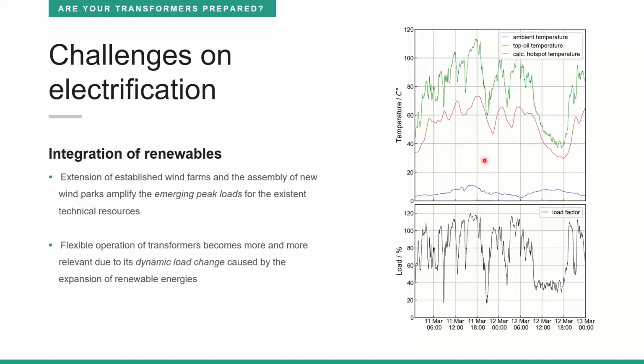And this high load, of course, results in increased temperatures in the transformer. In the red curve, we have the measured top oil temperature of the transformer, which does not seem so high at first glance, because we have quite low ambient temperatures at that time. But if we calculate the hotspot temperature, the hottest point in the transformer, based on load and top oil temperature, we can see that we already have quite high temperatures.